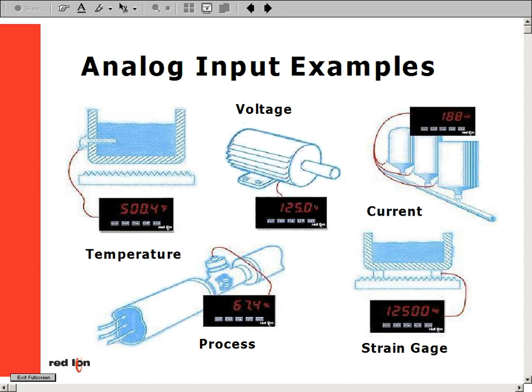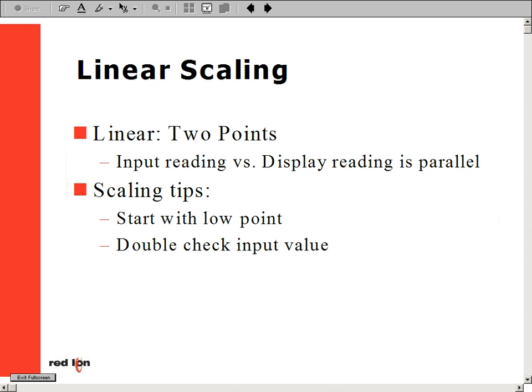Linear scaling of an analog signal is the most common type of scaling you can use to display a value different than your input. Linear scaling consists of 4 points: a low and high point of your input signal, and a low and high point of your display reading.